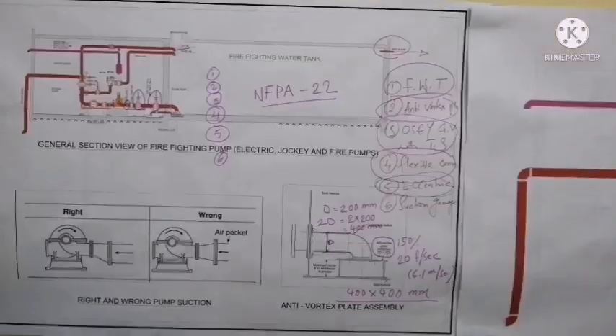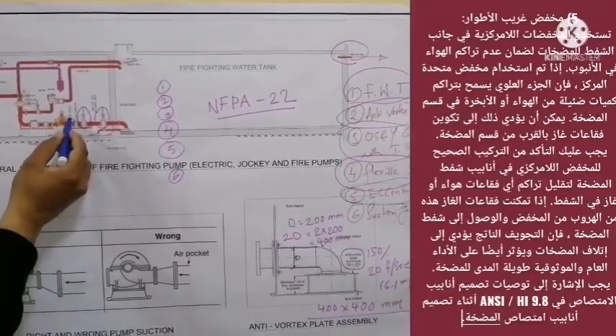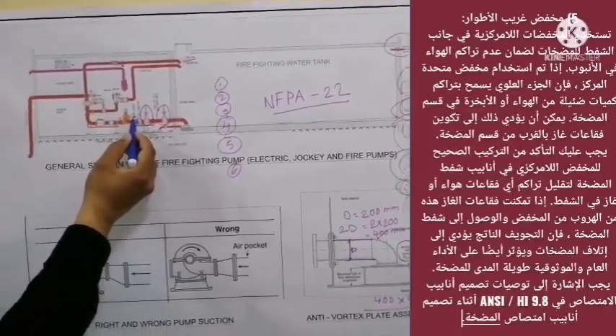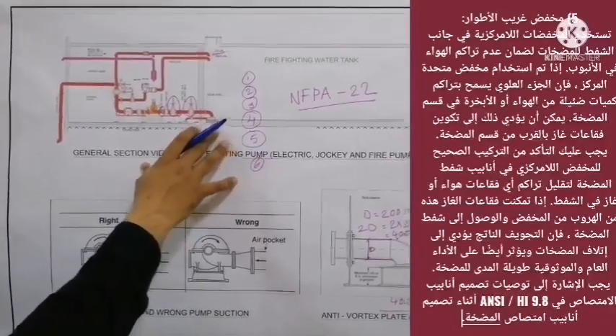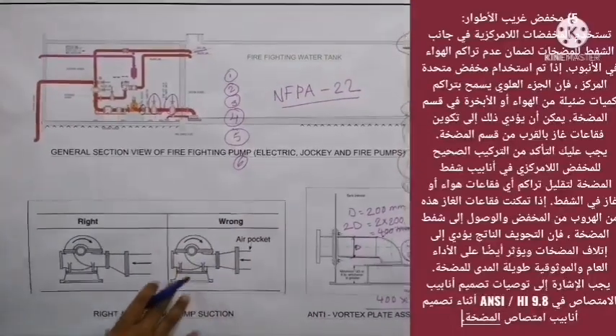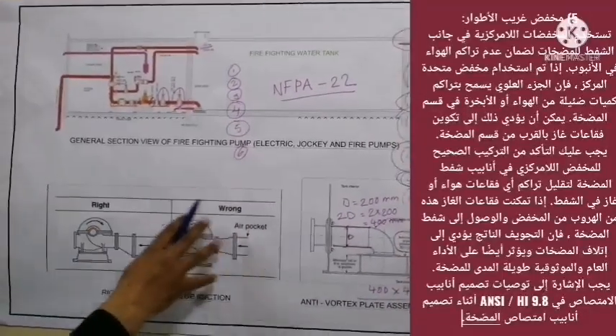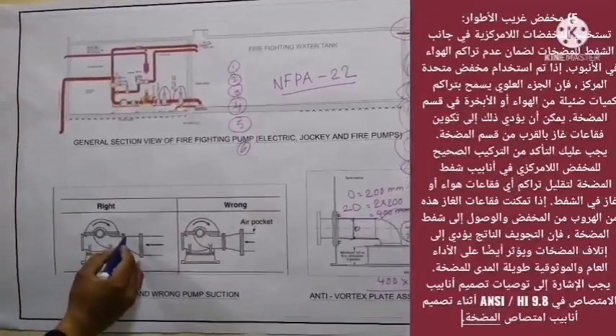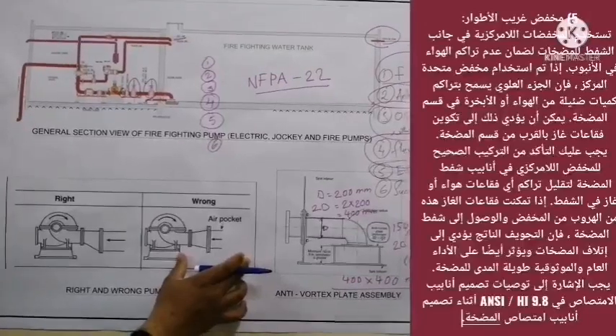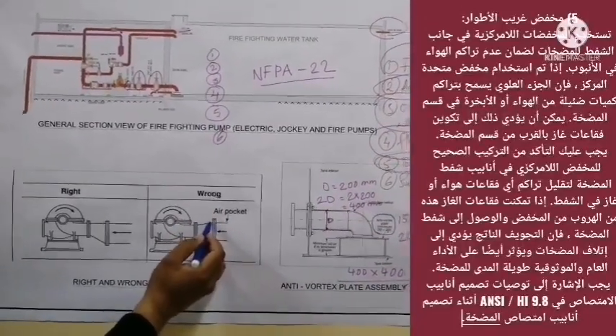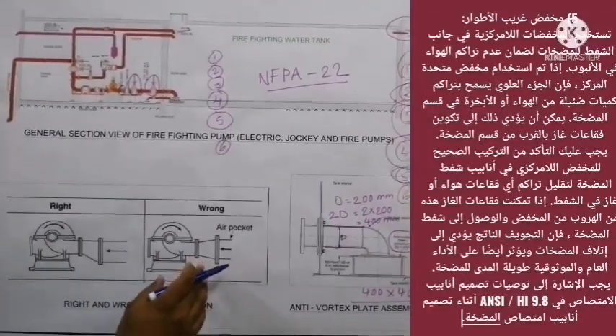Now let's discuss point number five — the eccentric reducer. You can have a look at the location of the eccentric reducer, which is installed before the flexible connection. Eccentric reducers are used at the suction side of a pump to ensure that air does not accumulate in the pipe. You can see clearly the difference between right and wrong suction installation. If concentric reducers are used instead, the upper part allows accumulation of trace amounts of air or vapor in the pump suction, which can lead to creation of gas bubbles near the pump suction.